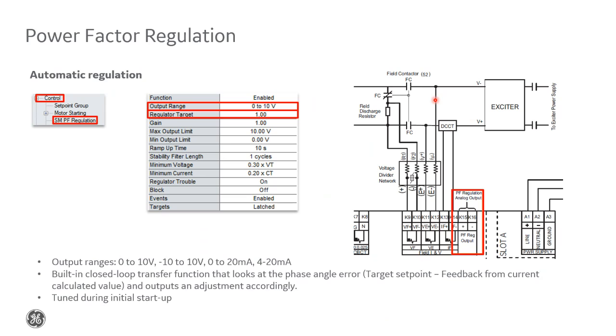This feature uses a closed loop transfer function that continuously looks at the phase angle error, which would be the target power factor set point compared to the real time calculated value. Based on this, it'll output a signal accordingly to adjust the field excitation. With the 869, we do have a wider selection of output signal types now to accommodate more excitation systems. So you can choose a voltage signal in the range of 0 to 10 volts, minus 10 to 10 volts, or a current signal of 0 to 20 milliamps or 4 to 20 milliamps.